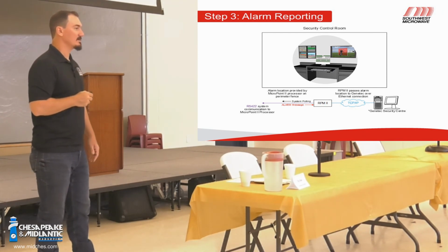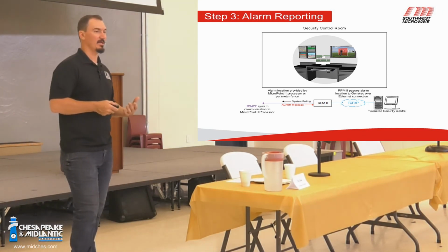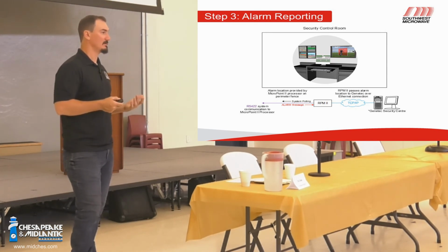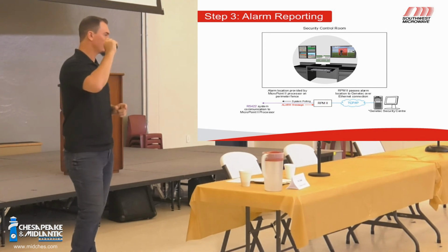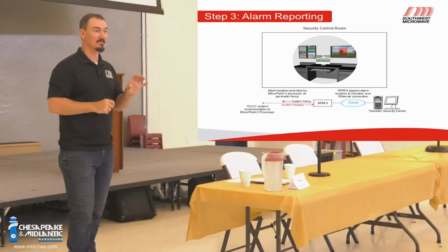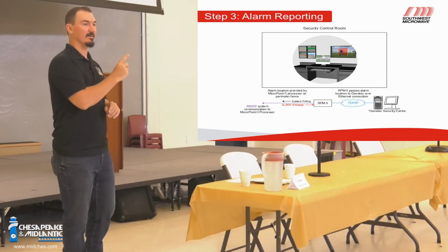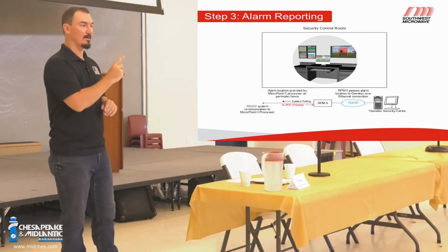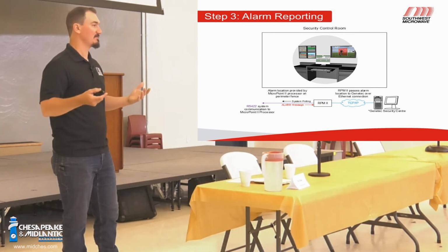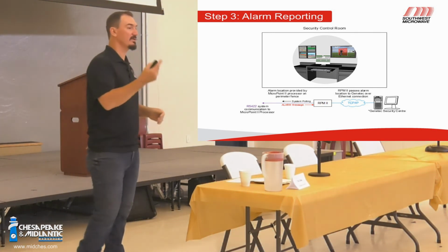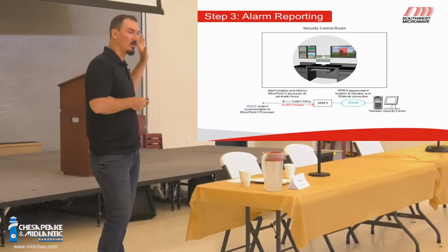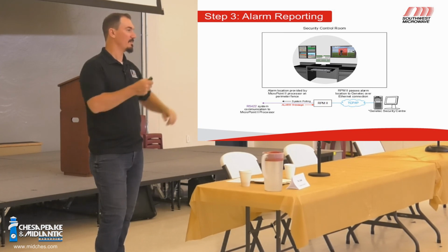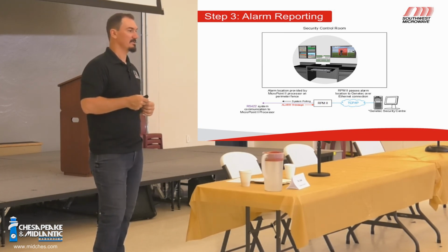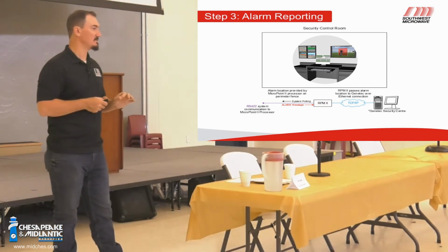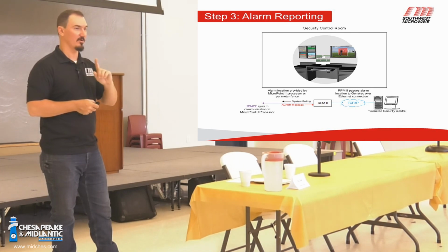If you're using the software integration, your head-end device is going to be called an RPM, a remote polling device, or a remote polling module. So the RPM is a small circuit board. It's got a little RJ45 network connection on it, and it's got a USB-A type plug on it. From that device, you can plug in and reach any of the processors on the fence. Okay? So if you're troubleshooting, or if you're trying to find a status of something, if we are troubleshooting with you and we say, hey, pull an event history on one of the processors, you don't have to go all the way out to your perimeter to do that. You go to your control room, plug into the RPM, retrieve that. Same thing if you're using the control module, the CM2. From the CM2, you can plug into that and retrieve anything from any of the processors on the fence as well.